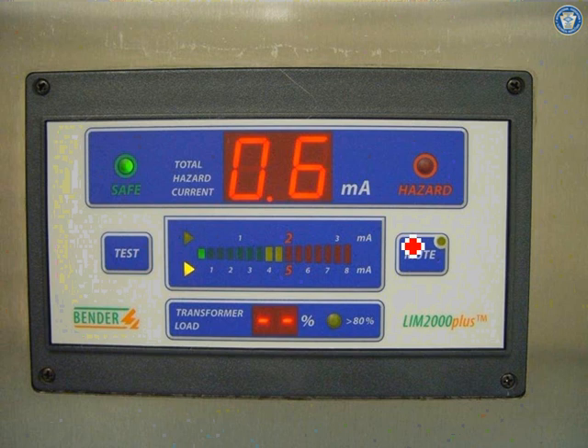This is typically what we believe to be measuring leak current. You're measuring the current coming in and coming out, and if there's a substantial difference coming into phase A, phase B, phase C, and there's no neutral, and the ground, if there's substantial current coming on the ground, then you have a grounded system. Here's a couple of nice pictures.